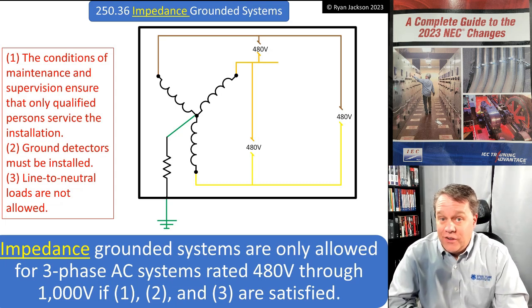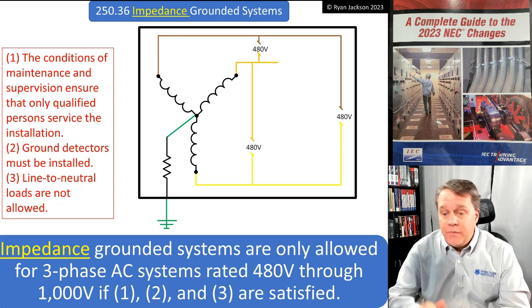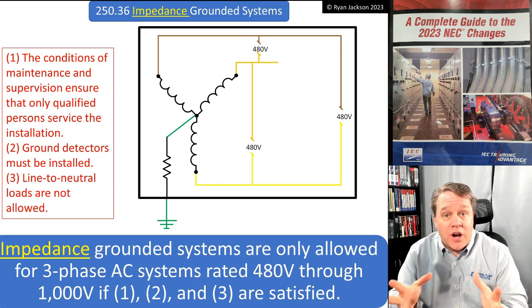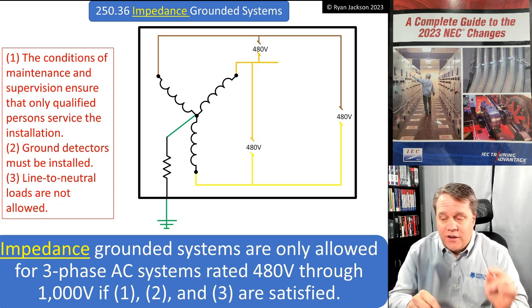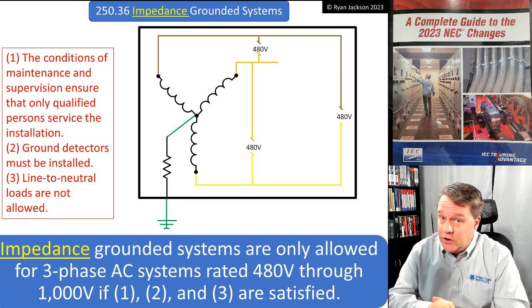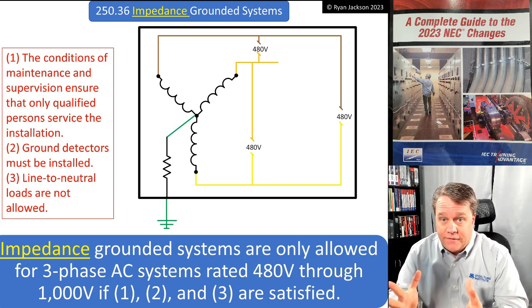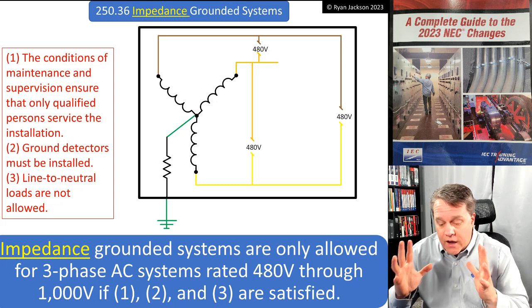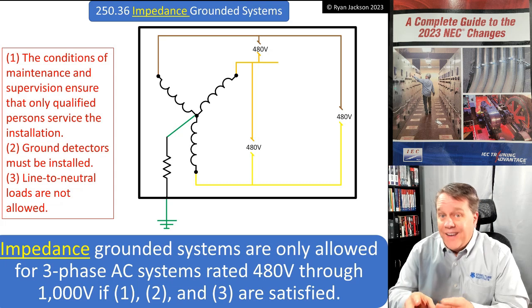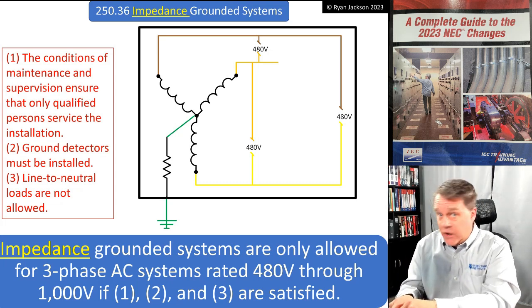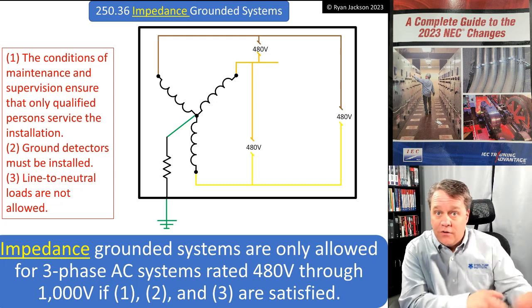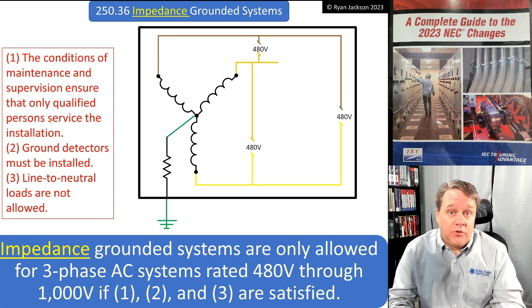But we also used the word 'neutral' in 250.36, and an impedance grounded system does not have a neutral. I reached out to my friend Chuck Mello - shout out to Chuck - he was on Code Making Panel 5 for a long time.